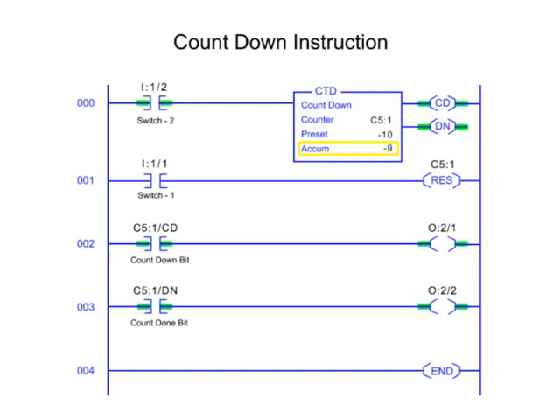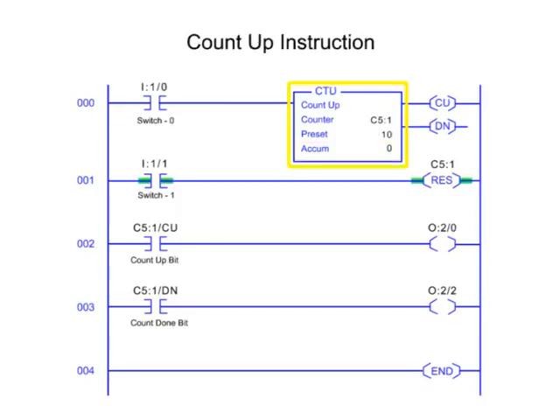After the accumulated value reaches the preset value, the counter instruction done or DN control bit is enabled. The accumulated count is retained until cleared by the reset instruction addressed same as the CTU file.